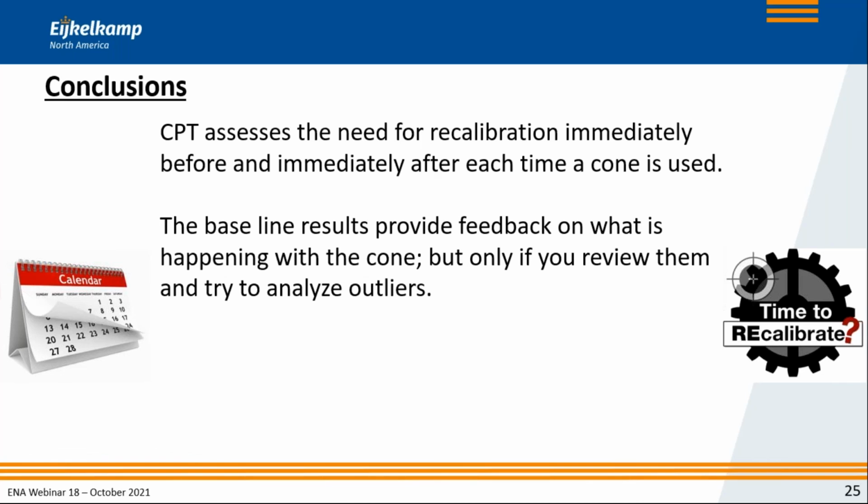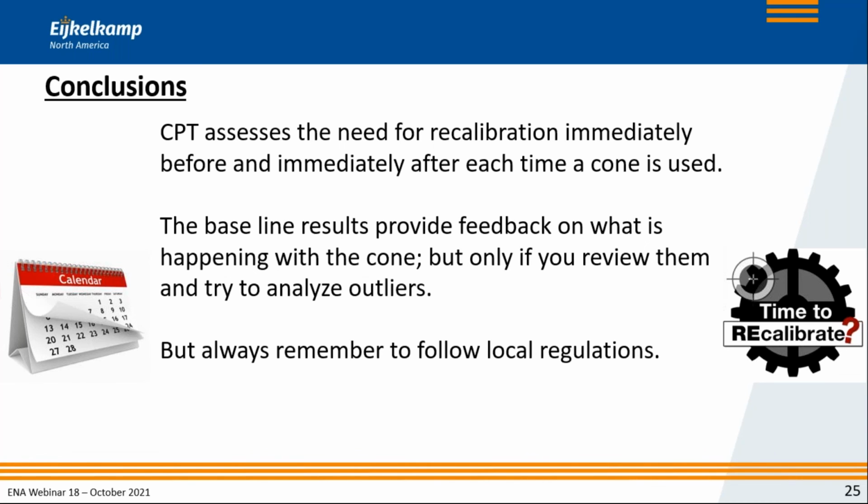Those baseline results provide excellent feedback on what's happening with the cone, but only if you analyze them. And quite often what I see, I did an audit not too long ago, I asked them, do you have all the baseline readings? They handed me a folder, nicely printed out, dated, everything there, what the project was. I said, did you look at them? Nah, we print them and we put them in the folder and that's it. Well, that's not really what I would recommend.